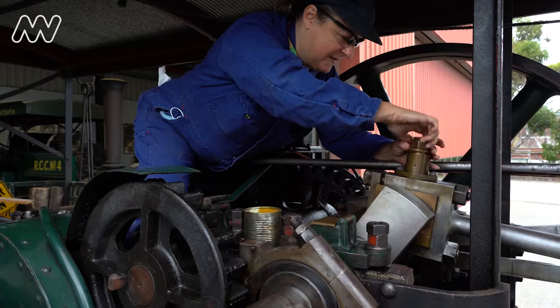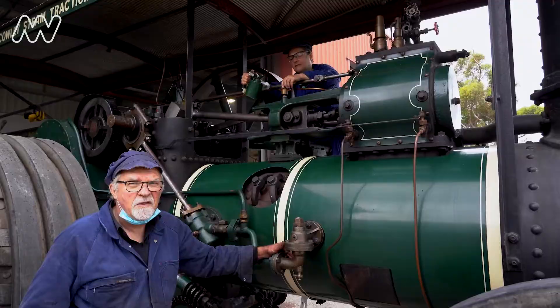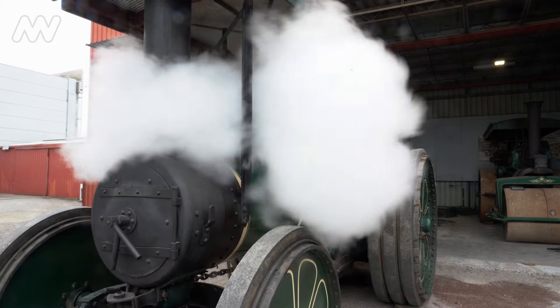It's not time spent idle. The engine's moving parts must be inspected and lubricated and the manhole door tightened as the pressure builds. But what stops that pressure from building too far? There are two safety valves fitted on top of the boiler. If the boiler pressure increases above the working pressure of the boiler, those safety valves will lift and let the excess steam escape.